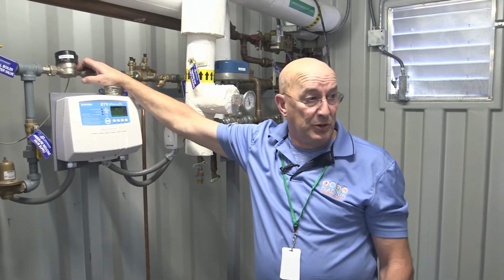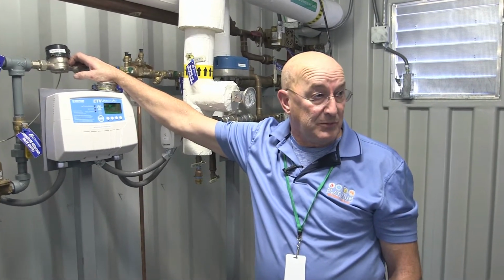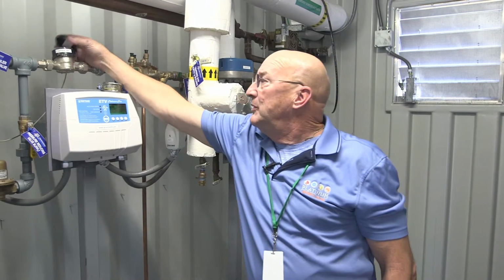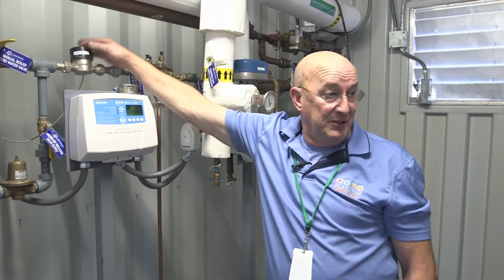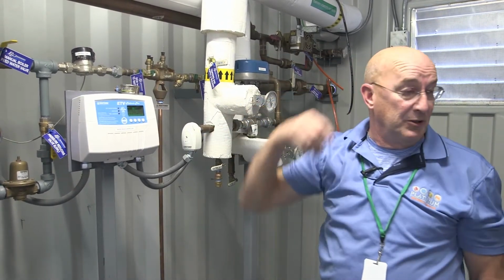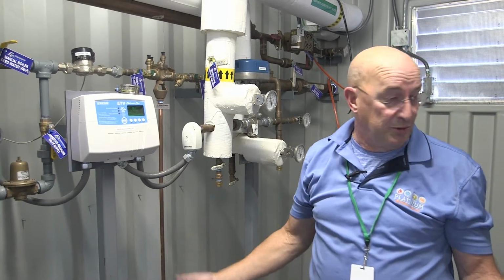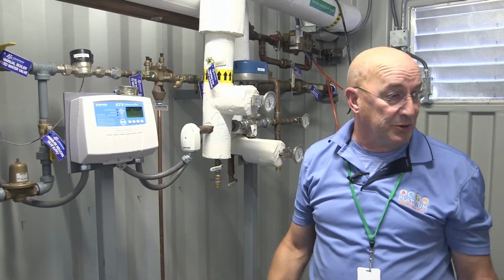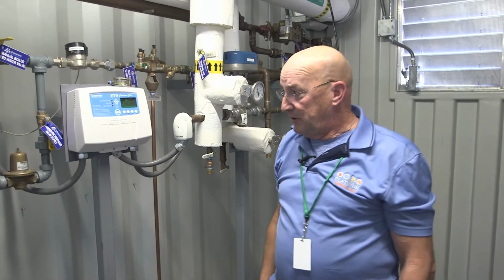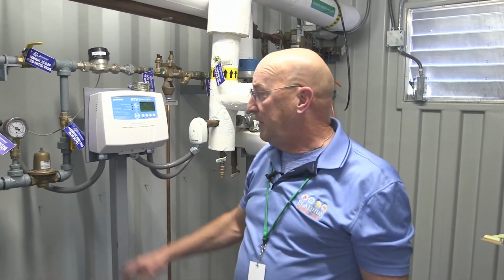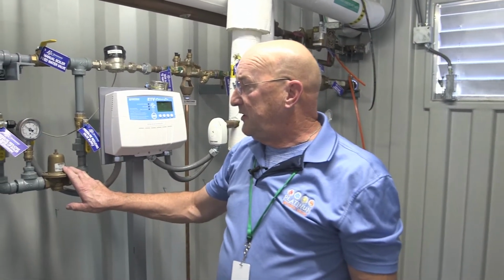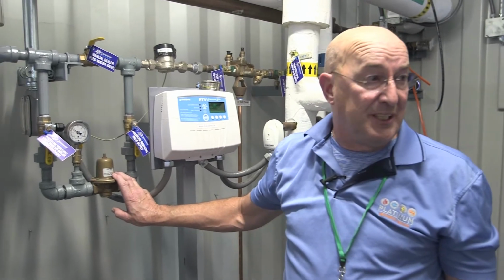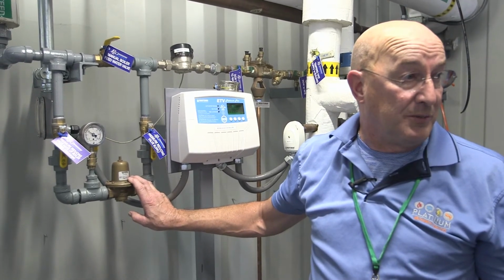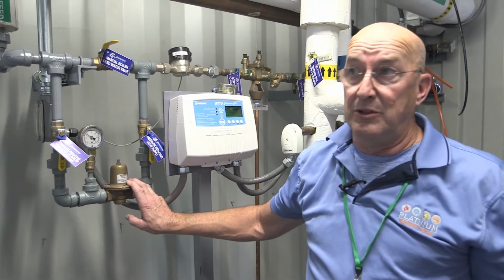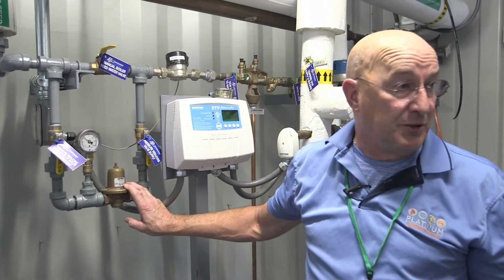That means there's water loss in the heating system somewhere. You open this up and you'll see it spinning. Otherwise, whoever's watching the computer will get a reading that you're using excessive water. This feeds the water to the boilers and should maintain 12 pounds of pressure at all times, so that you know there's pressure in the system and everything will run well.